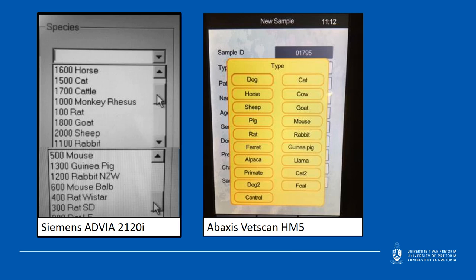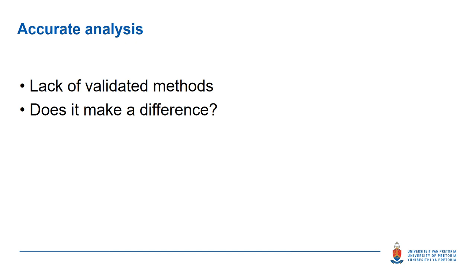If we look at the species settings available for two fairly common hematology analyzers — the ADVIA 2120 and the Abaxis Vetscan HM5 — we can see that the settings provided are for domestic animals and not for wildlife. Even with the ADVIA, species like rhesus monkeys and mice are present because they are commonly used as lab animals, and ferrets, alpaca, and llamas are domesticated. So effectively, we have a lack of validated methods or species settings for unusual animals, and I'm going to show you a couple of examples of how it does actually make a difference.